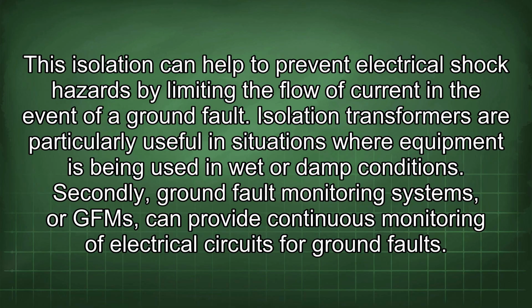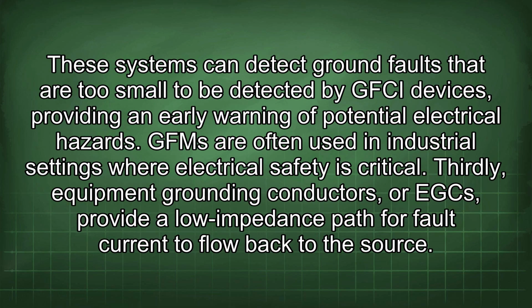Secondly, ground fault monitoring systems, or GFMs, can provide continuous monitoring of electrical circuits for ground faults. These systems can detect ground faults that are too small to be detected by GFCI devices, providing an early warning of potential electrical hazards. GFMs are often used in industrial settings where electrical safety is critical.